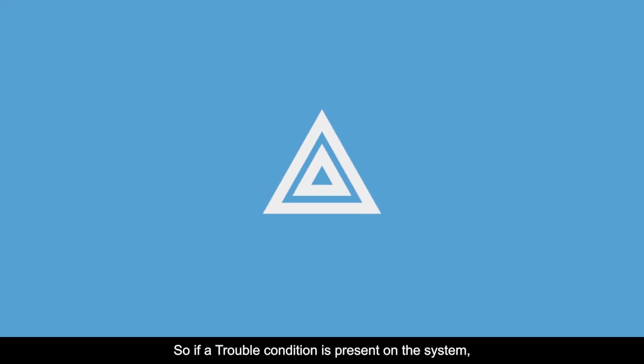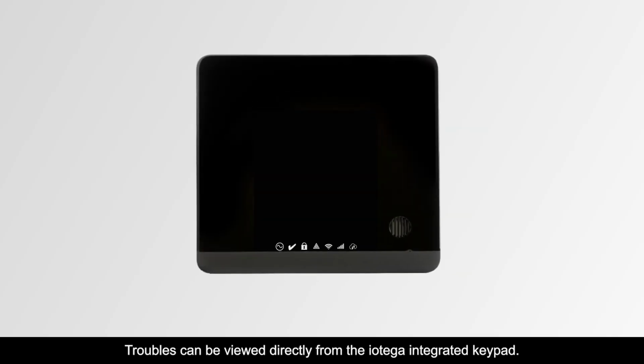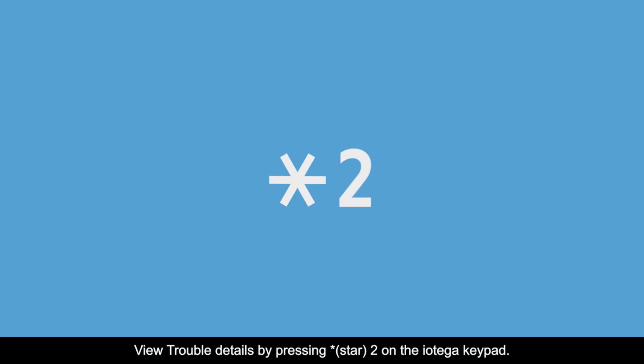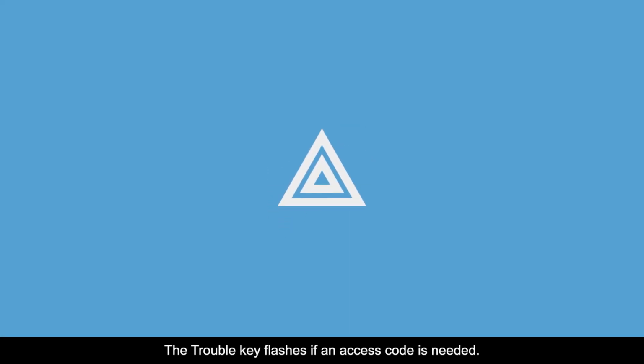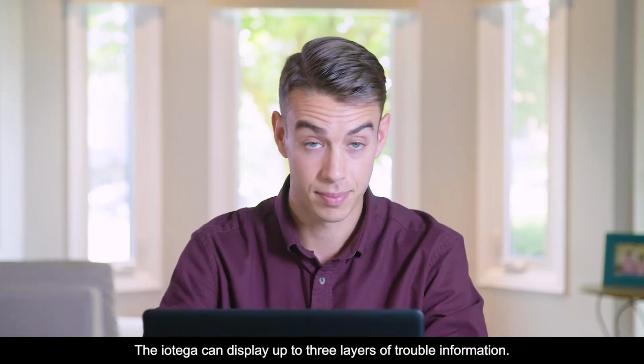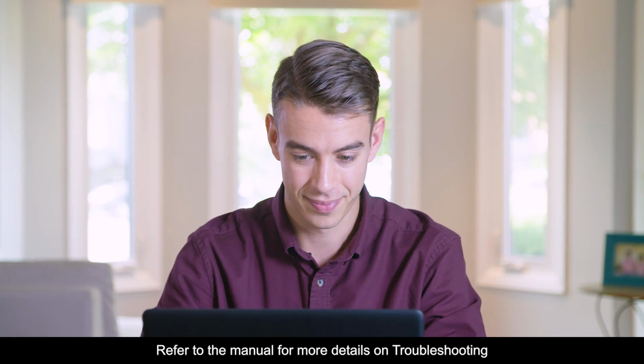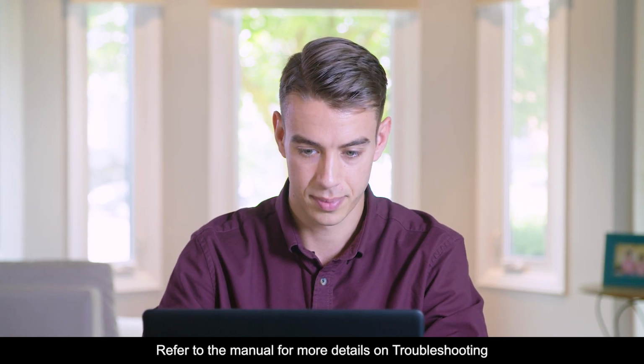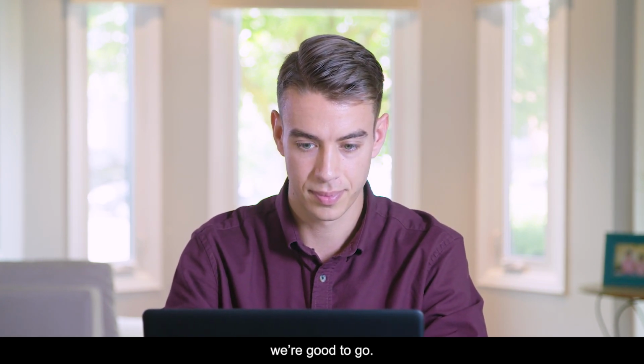So, if a trouble condition is present on the system, the trouble light keypad turns on, and the system beeps every 10 seconds. Note, trouble beeps are set to silent by default. Troubles can be viewed directly from the iotega integrated keypad. View trouble details by pressing *2 on the iotega keypad. The trouble key flashes if an access code is needed. The iotega can display up to 3 layers of trouble information. Refer to the manual for more details on troubleshooting. And that's it. We're good to go.